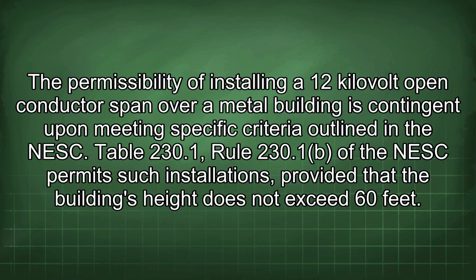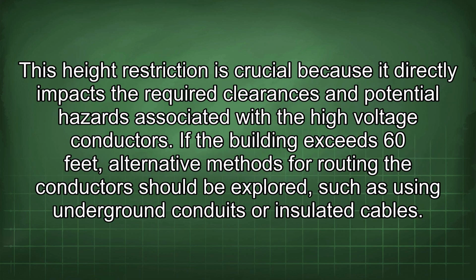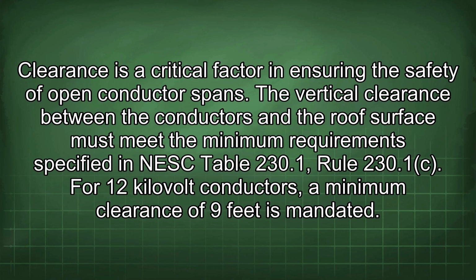Table 230.1, Rule 230.1 of the NESC permits such installations, provided that the building's height does not exceed 60 feet. This height restriction is crucial because it directly impacts the required clearances and potential hazards associated with the high-voltage conductors. If the building exceeds 60 feet, alternative methods for routing the conductors should be explored, such as using underground conduits or insulated cables. Clearance is a critical factor in ensuring the safety of open conductor spans.